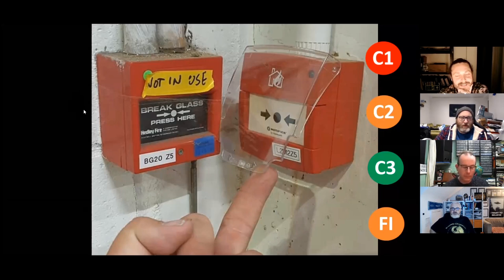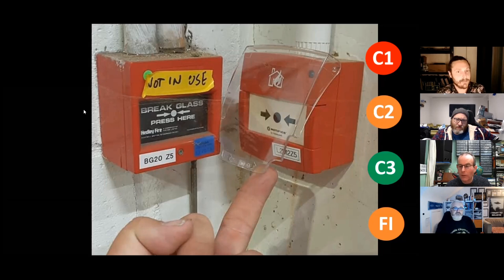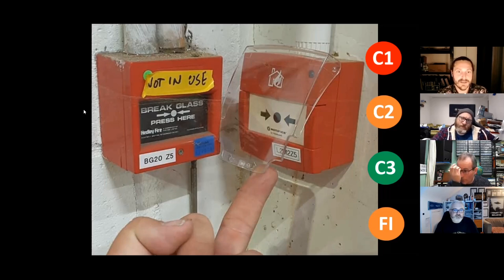What do you think? I'm going to be a bit brutal here. Just looking at that, let's assume that the system is being replaced and the old one will be ripped out, possibly. Well, maybe not actually. Not in use. Well, we'll assume it is, but it's a great indicator of making sure that your call points, your help points, are accessible. The purpose of the call point is to raise the alarm manually. Yes. So we have got smoke detectors, but again, it depends on what type of system you've got. This might be a manual only system, so we might not have smoke detectors here. Yep. But it's evident here, if there were a fire, and bear in mind, people are panicking, they're screaming or whatever, it's not like we are now where we're calm and collected. You want to act quickly. And if they can't act quickly, do you think they're going to operate the fire alarm and save everybody else in the building?